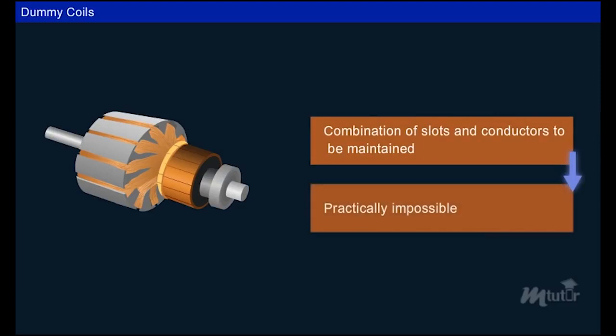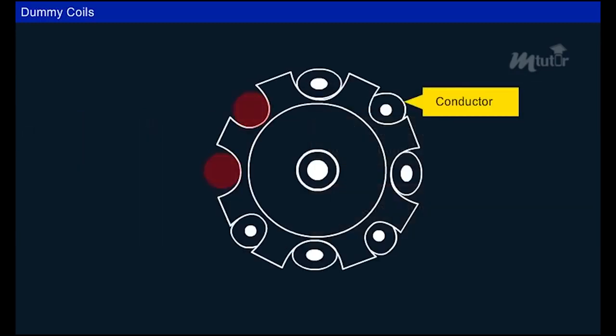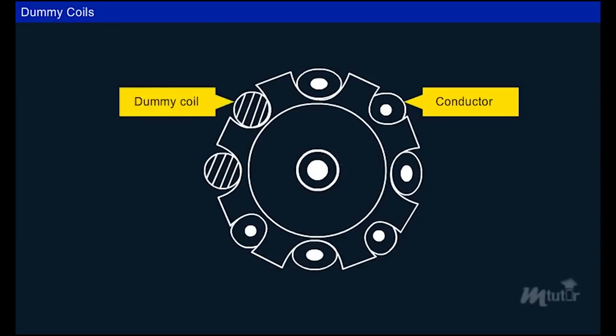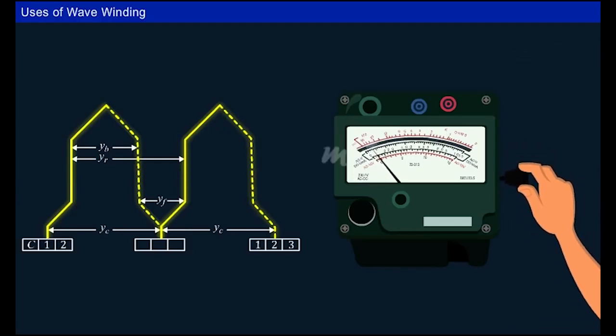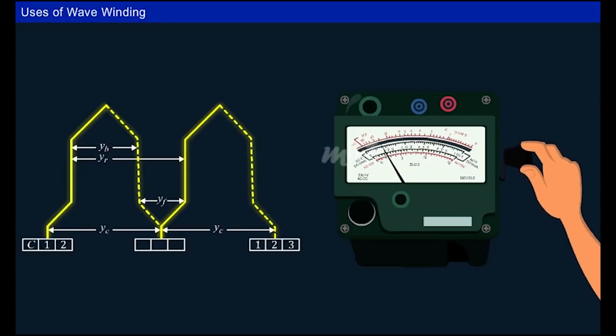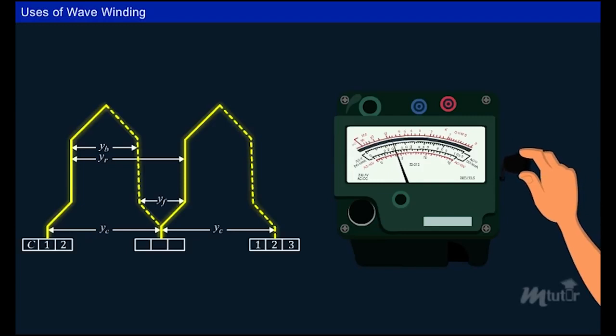For wave-type armature winding, a specific combination of slots and conductors is required. Practically it may not be possible to meet such design requirements, so to provide mechanical balance, one or more coils may be inserted in appropriate slots, electrically insulated from other windings — these are called dummy coils. In wave winding, coils are connected in series, so the voltage of each winding adds up while the current remains the same. Therefore, wave winding is used in high-voltage, low-current applications such as hand-cranked megohm meters for providing high test voltages.